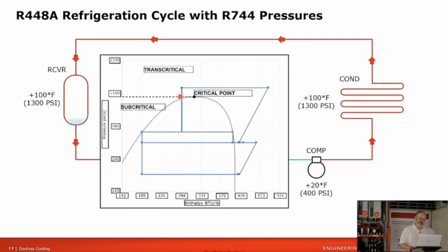But if you complete the diagram there to get liquid back into the system, think about what we can do to cause that to happen. Think about the expansion valve. On the low side of a typical HFC system, we use an expansion valve to get us from the high side to the low side. No different with CO₂. On its high side, we're going to use an expansion valve. We call it the high pressure valve, but it's basically just a large expansion valve.